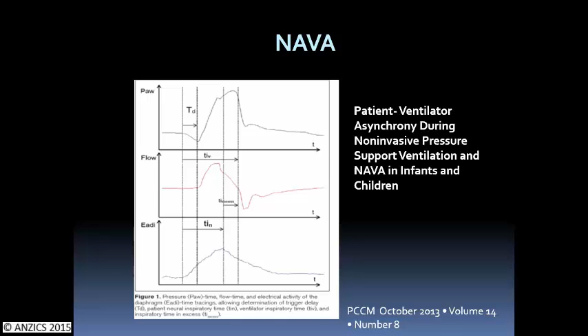It does have a backup. If the signal's not good and it can't trigger on that, it will trigger on flow. It'll flow trigger in if it doesn't trigger on the neural signal, and it'll flow trigger out as well, so it doesn't keep making you breathe in if it loses the signal halfway through.